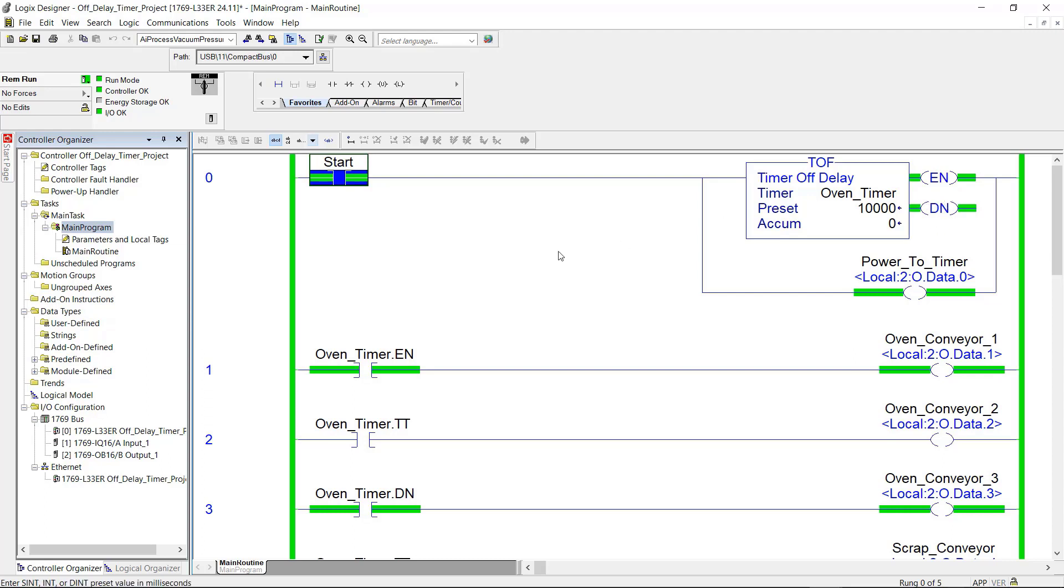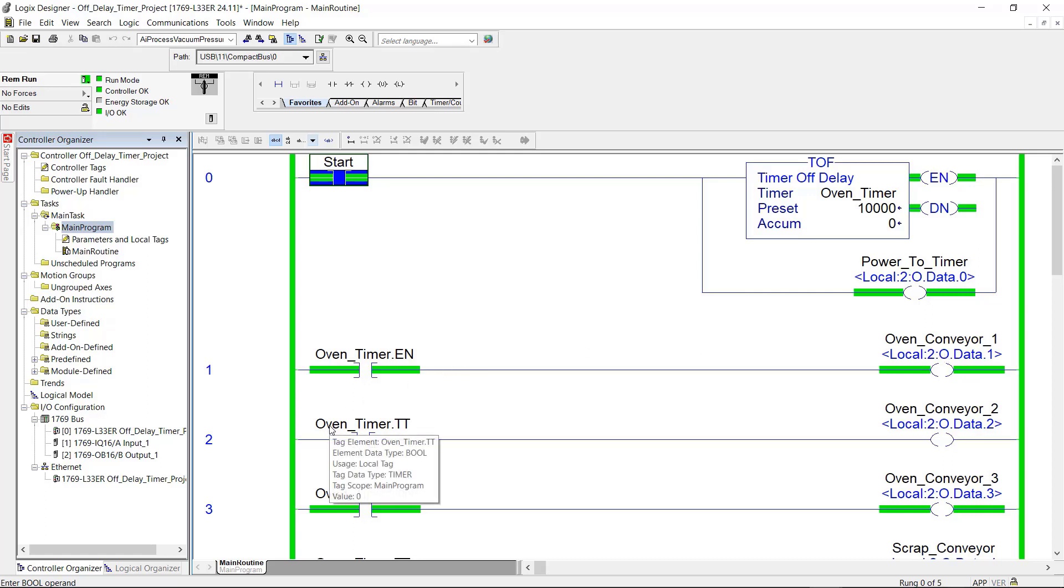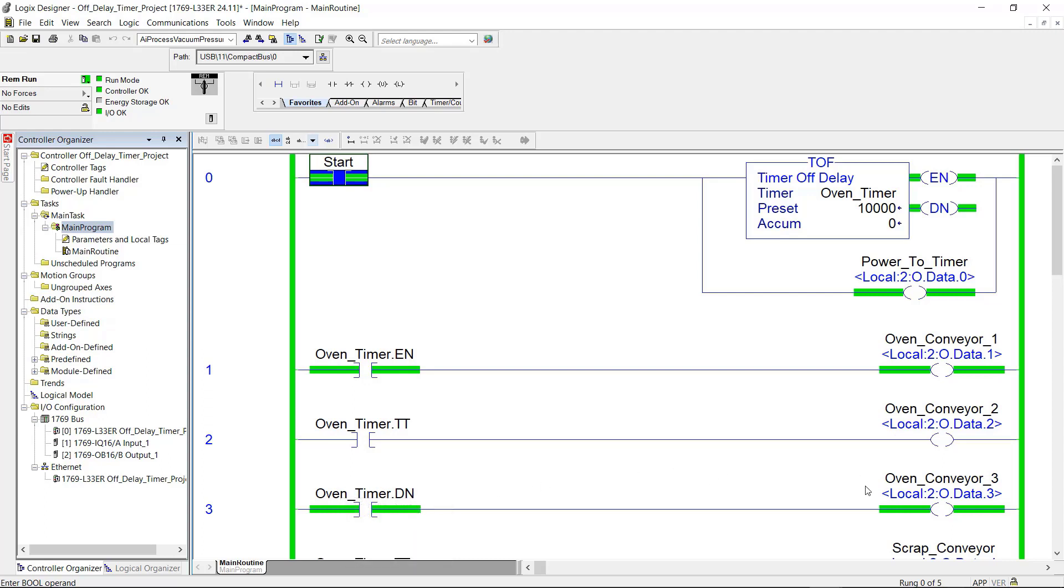My enable and done are both true here. And if I come down here to rung number one, the enable bit here is true. So the output is true. Come down to rung two, the timer timing bit is not true because the timer is not timing. It is not accumulating time. And the output for that rung is not true. Now the done bit is true. And the done bit's output is true.